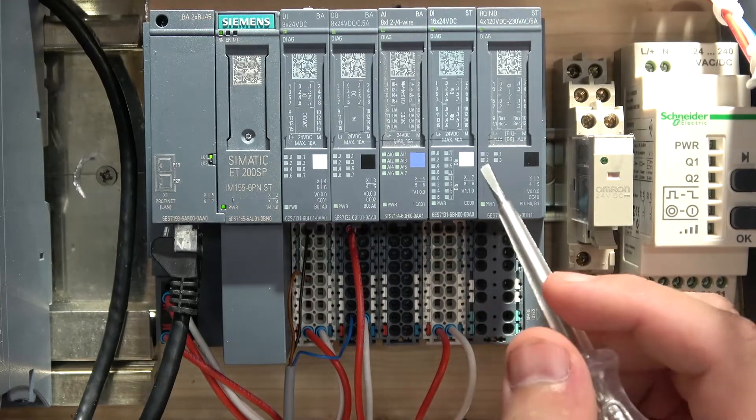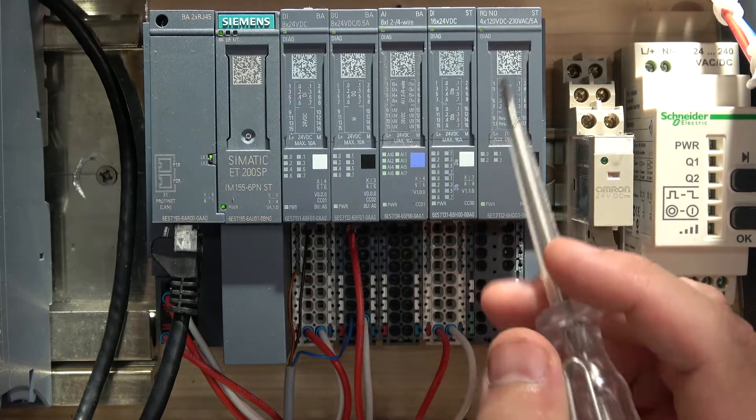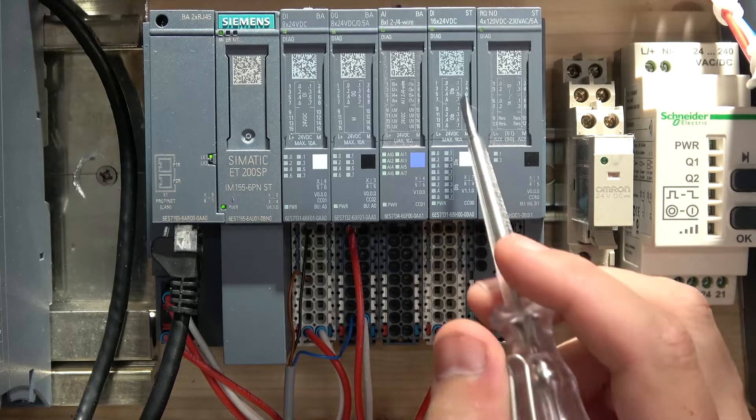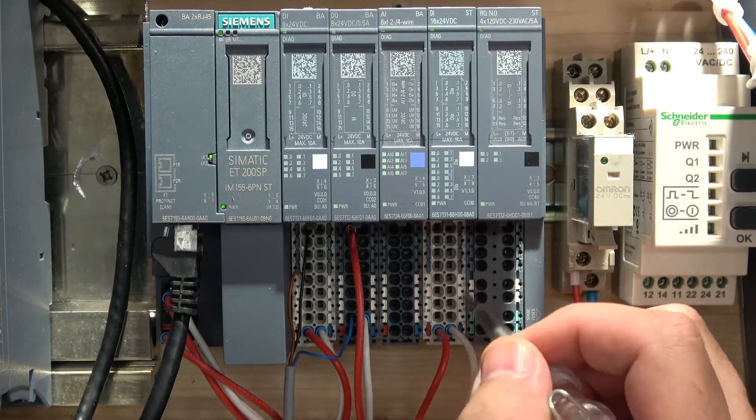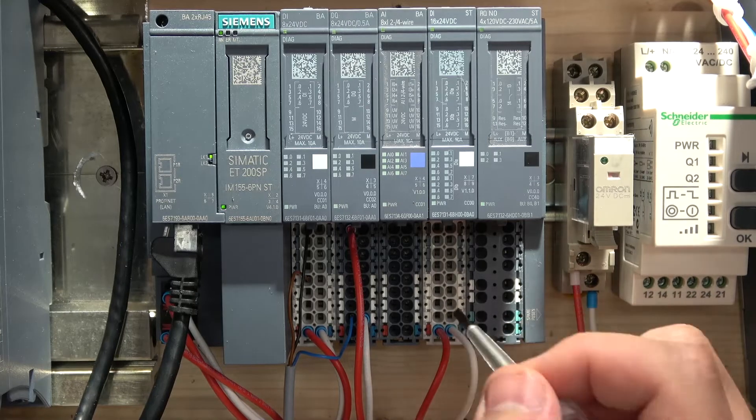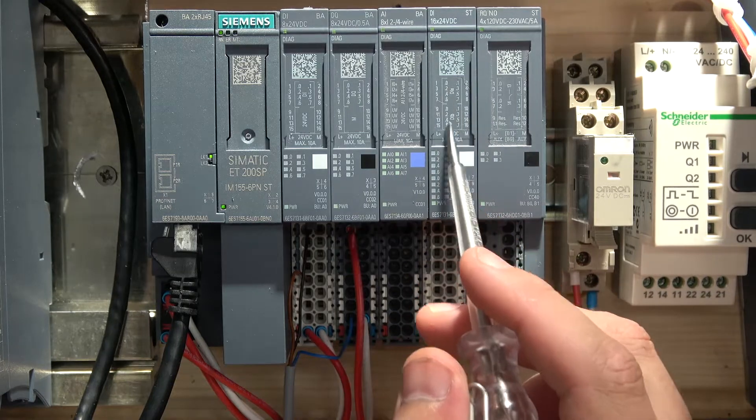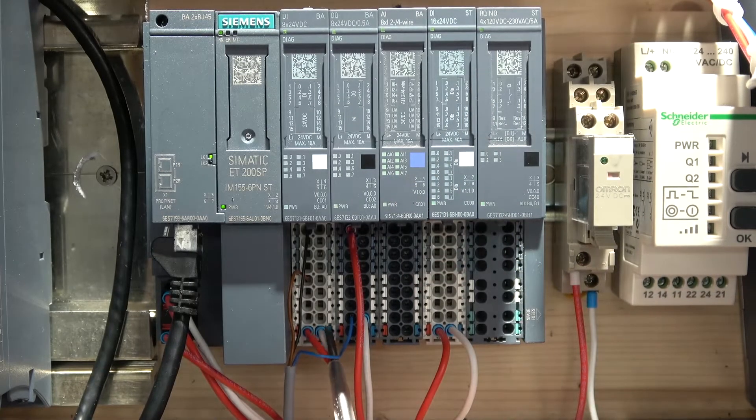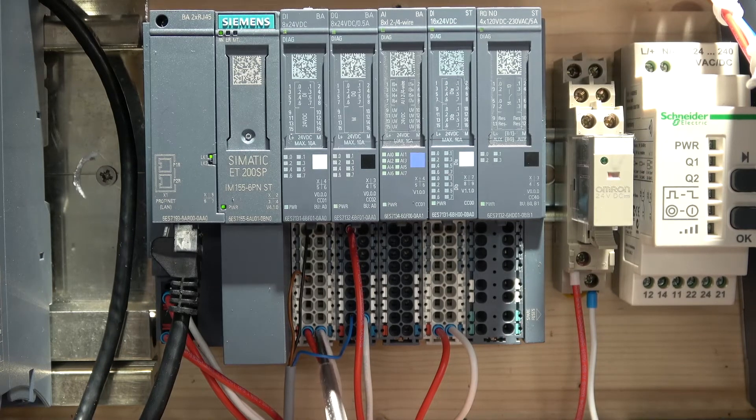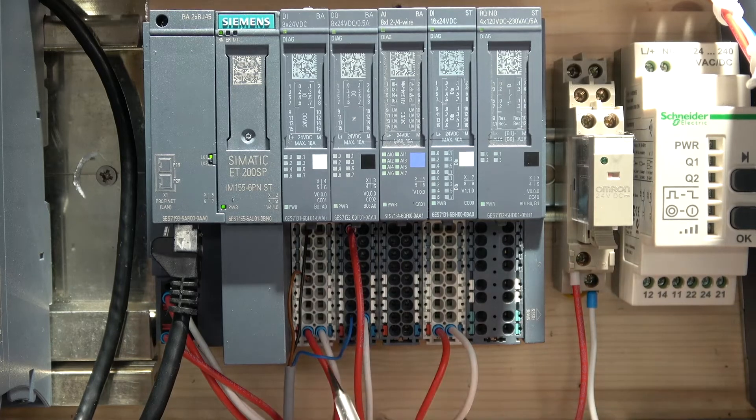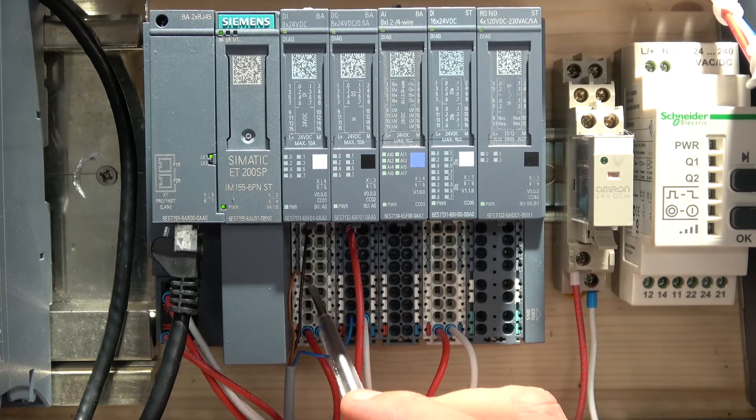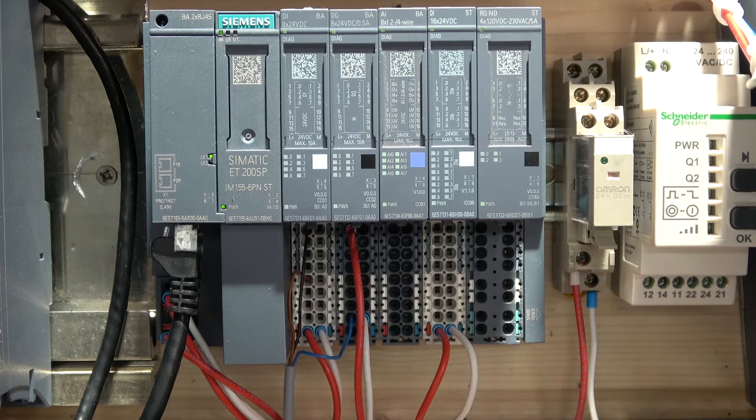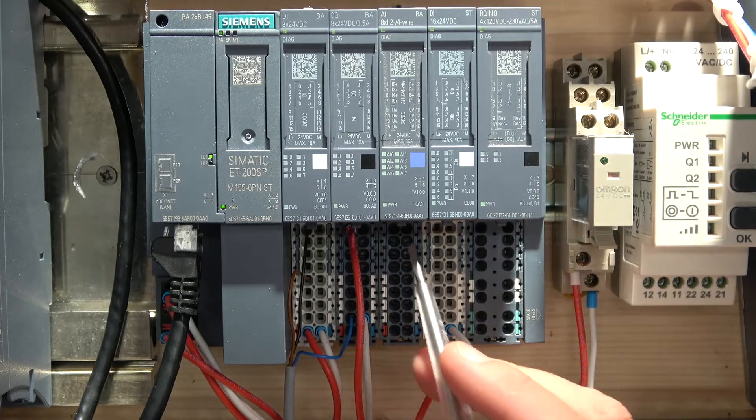But if you look at it, I specifically added another card which is 16 digital inputs. Both sections have been occupied as input, so the pluses will have to return to all of these. Do make sure you understand where this power supply is coming from, because the sensors and everything else coming back to these cards has to be from the same power supply. If I'm powering the induction sensor, I'm going to be sending a plus from here and a minus from the same power supply.